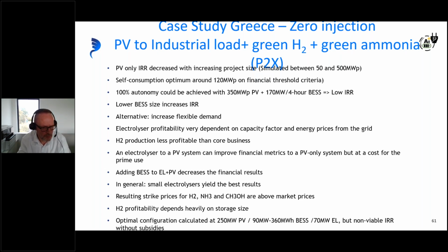Due to the zero injection constraint, we found that the bigger the PV system, the lower the project's IRR—so we simulated sizes between 50 and 500 megawatts. Without added demand side, the IRR decreases and the project size would need to be significantly reduced. Looking at self-consumption, there was an optimum around 120 megawatt peak based on financial threshold criteria, which didn't fully use the available land plot if considering only the factory load. For 100% autonomy, you'd need 350 megawatts of PV plus a 170 megawatt, 4-hour battery, but the IRR would then be too low for a viable business case. So there are several parameters you can adjust to optimize a business case toward your objective.